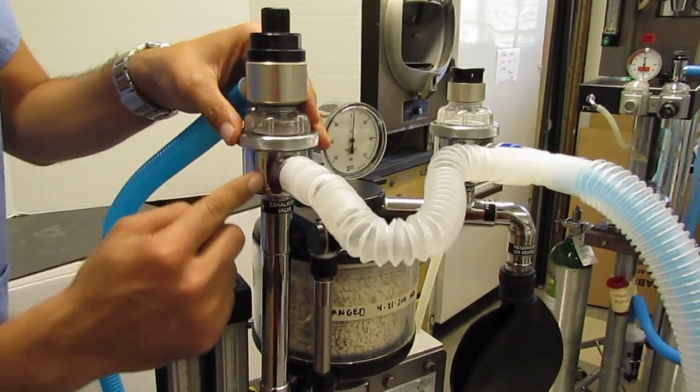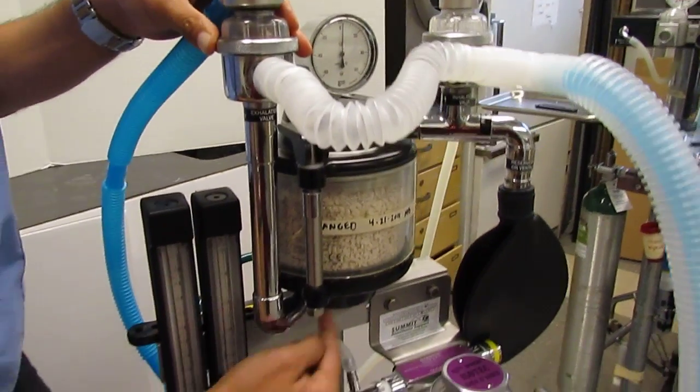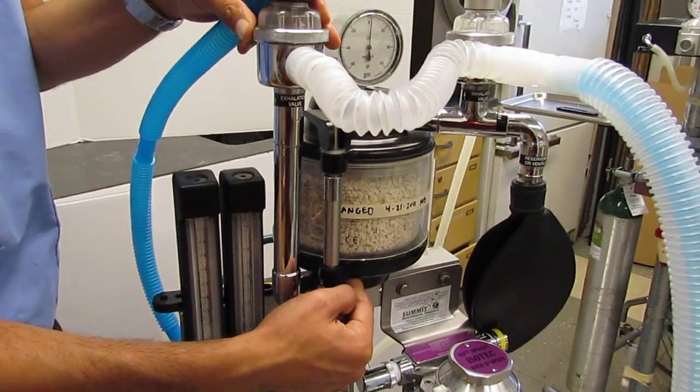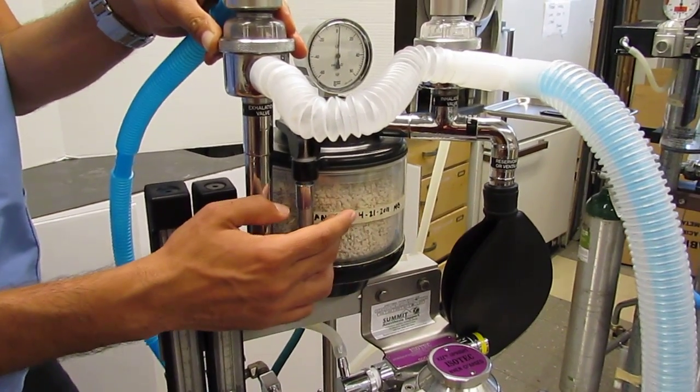The other place that it can go is that it can be recycled back in to the inspiratory system via this CO2 canister.